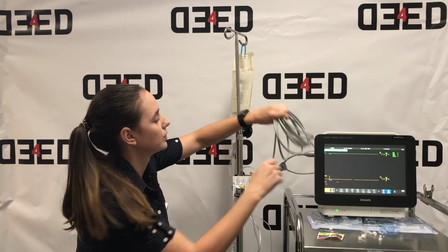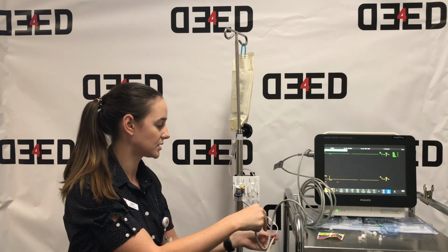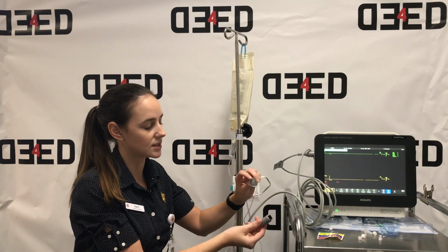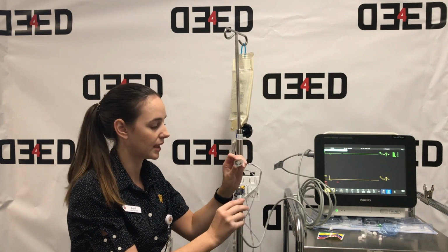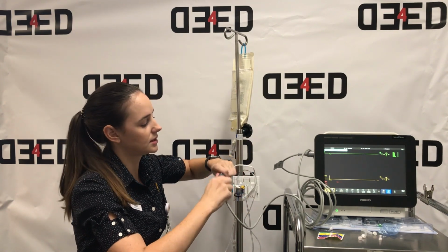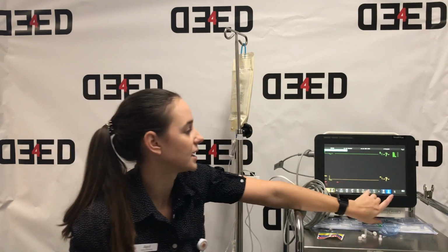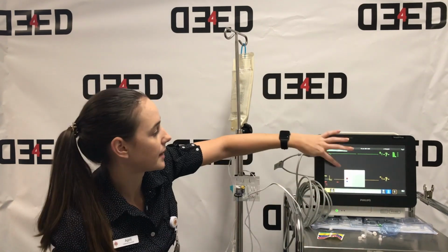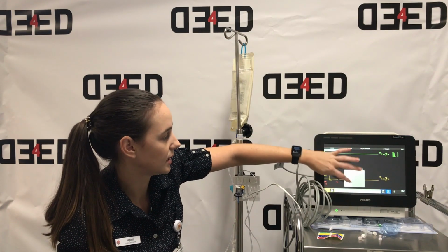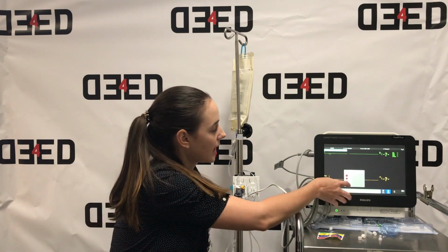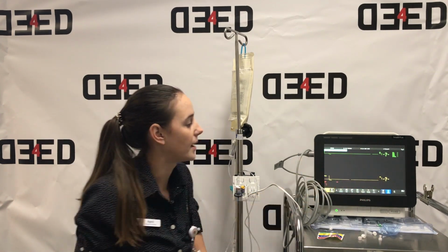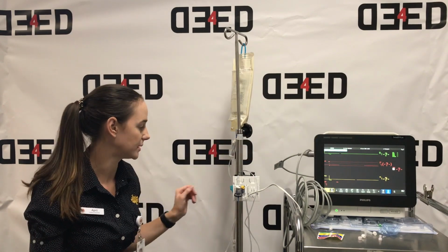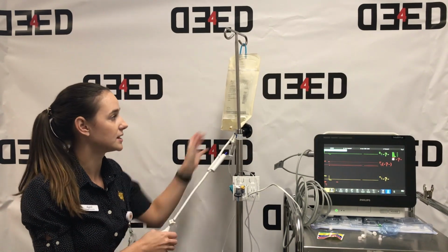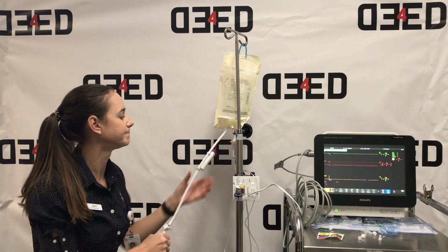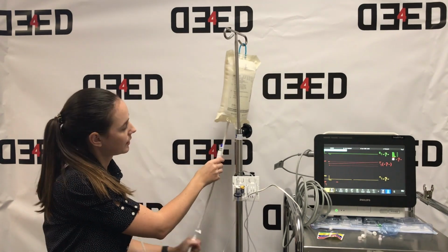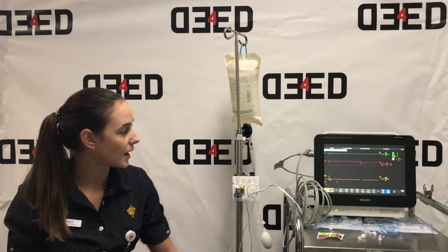Get your transducer cable from the monitor and connect that to your transducer kit. You'll see that there's a triangle marked on the cable from the kit and the cable from the monitor. Click those in. You'll hear it click. Come over to your machine and check your equipment and make sure that your arterial line is actually activated. Once you activate it, you'll see that it will come up on the monitoring screen there, ready to be used. The next thing you want to do is inflate your pressure bag to 300 millimetres of mercury, or the green zone. Perfect. All right. Now you are ready to go.